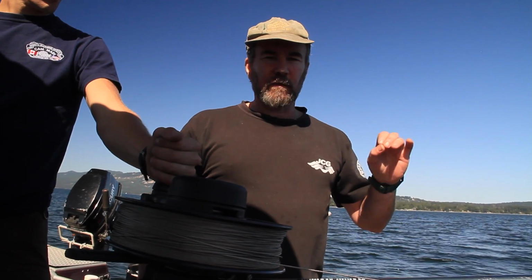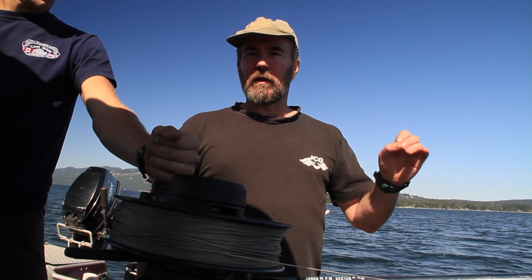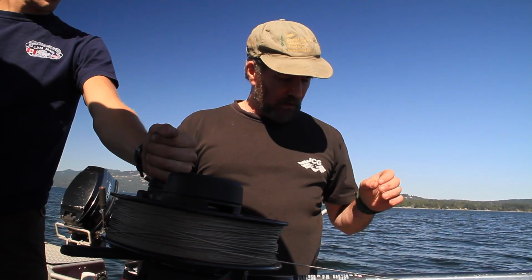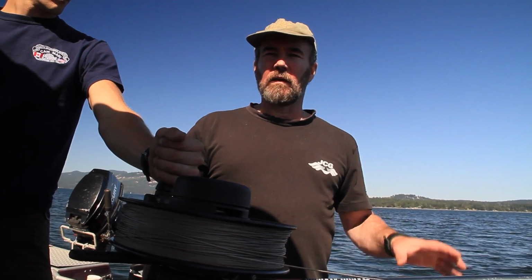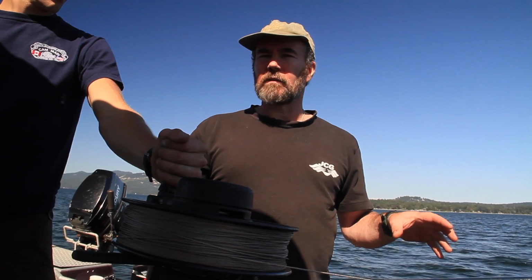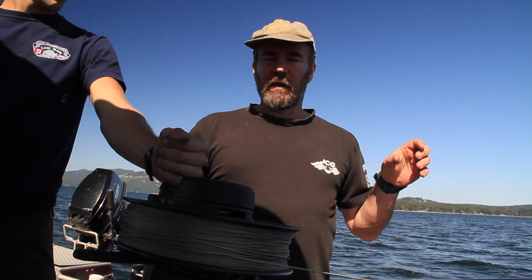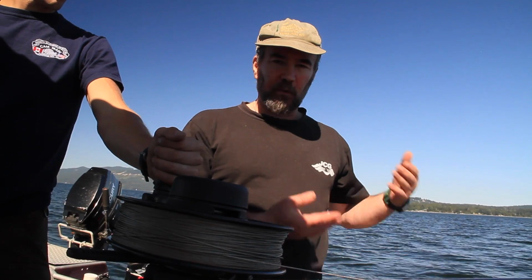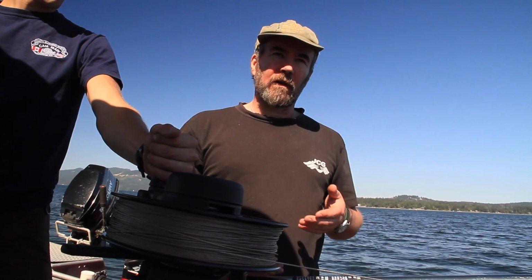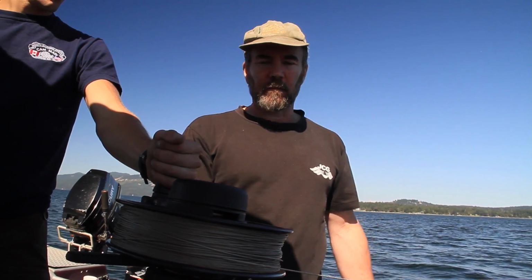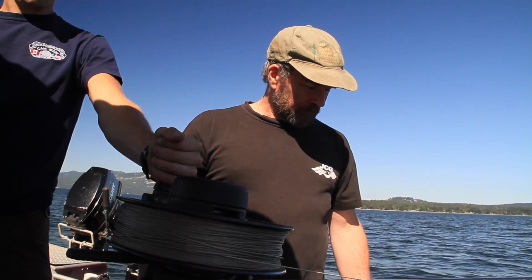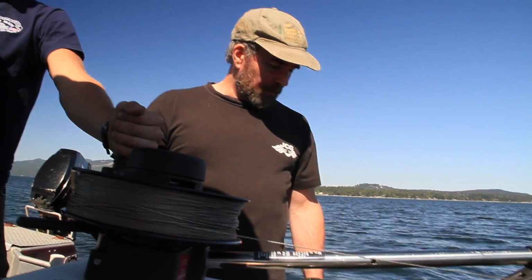The temperature sensor itself is very small. It changes temperature very quickly. The body of the CTD will actually contain some heat. So if there's a big disparity in temperature, then you have to make sure that you cool down the body of the CTD, because it will have a self-heating effect on the temperature sensor. So we leave it there, we make sure everything's happy.